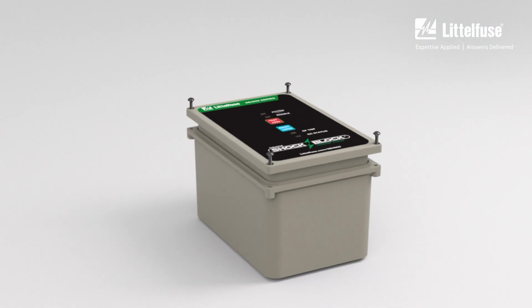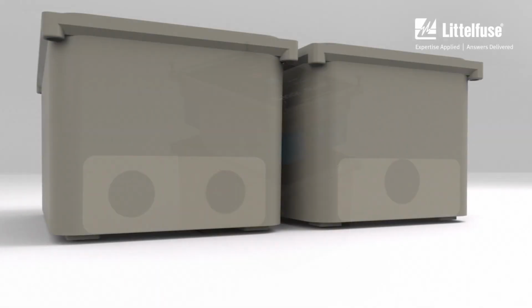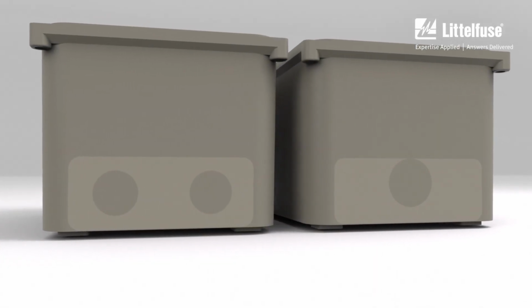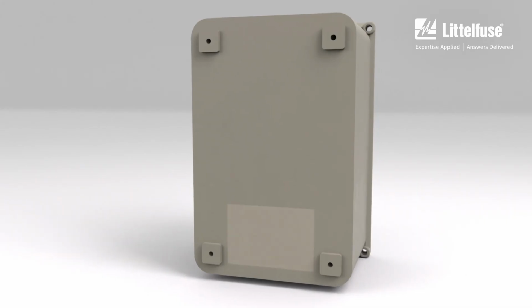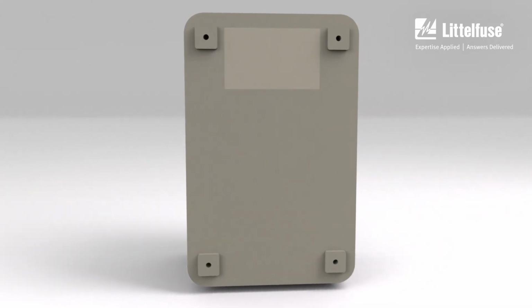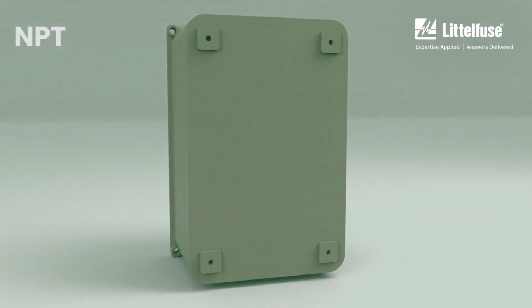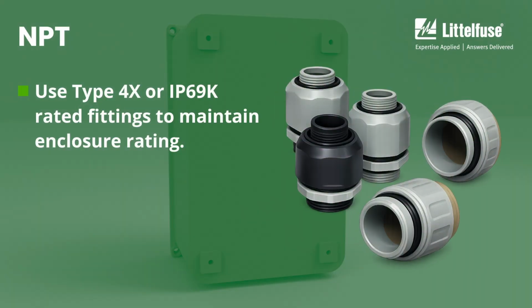Remove the base module using the 4 captive screws. The enclosure supports dual half-inch NPT or a single 3/4-inch NPT conduit. Use Type 4X or IP69K rated fittings to maintain enclosure rating.